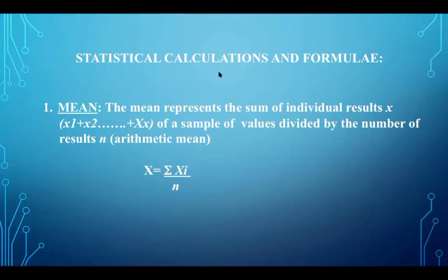So what we can do for our laboratory, we can say, whatever mean and standard deviation the manufacturer is offering to us, our mean should not be more than one standard deviation away from the manufacturer mean. And our standard deviation shall not be wider than the manufacturer standard deviation.